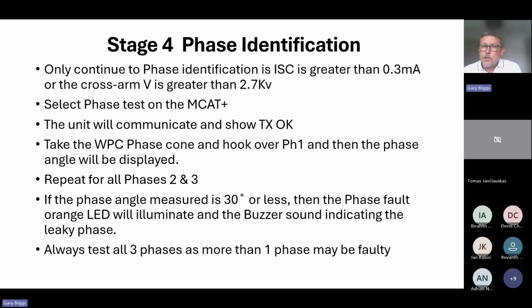But we wouldn't just do phase 1. We'll always do phase 1, phase 2, phase 3. If the phase angle measured is 30 degrees or less, then the phase is considered to be in phase, and that indicates that's the phase that's broken down. Now, there are occasions where you may have more than one insulator broken down. So you might find that phase 1 and phase 3, for example, both show as in phase.